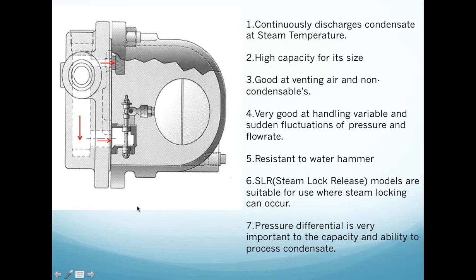Now, I have to tell you that these particular traps that I've showed you, the first two, are very good at processing condensate. But the one thing I want you to know is that none of the traps that we're going to discuss today have the ability to generate any additional pressure to help promote the evacuation, or the push, if you will, of condensate out of the heat exchange area. These particular traps are going to process condensate, and I need you to position these steam traps so that we have gravity working on our behalf, allowing condensate to fall into the body and then fall out of the trap and into the condensate return system.